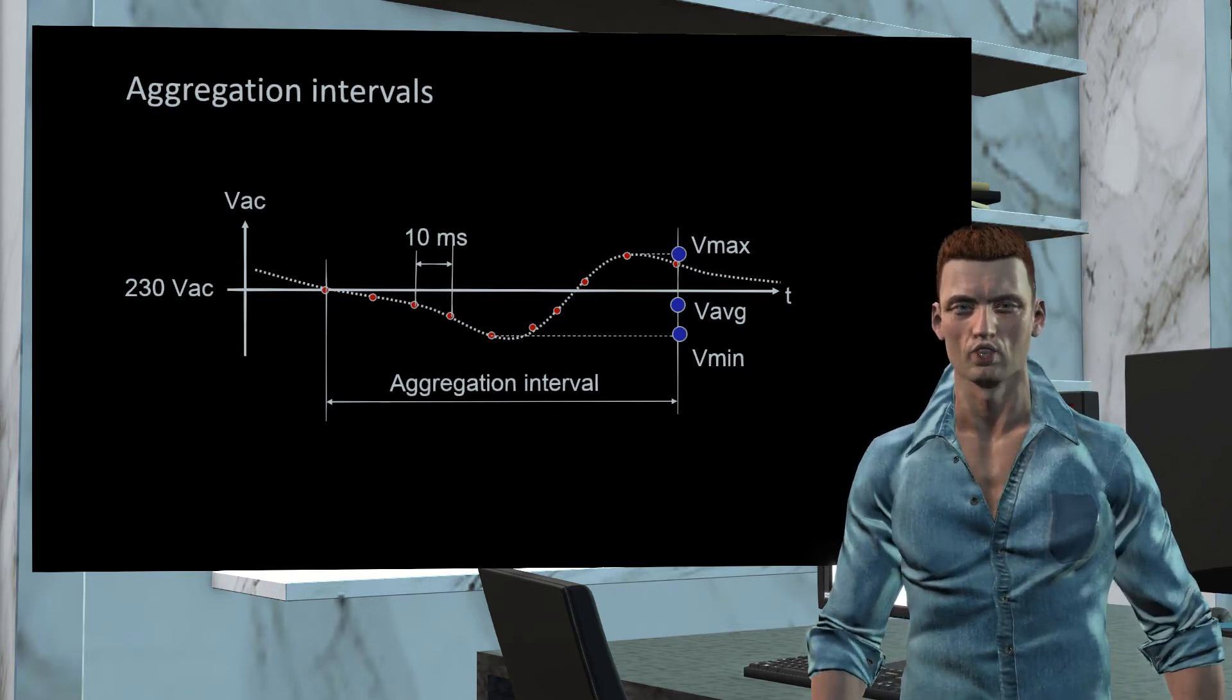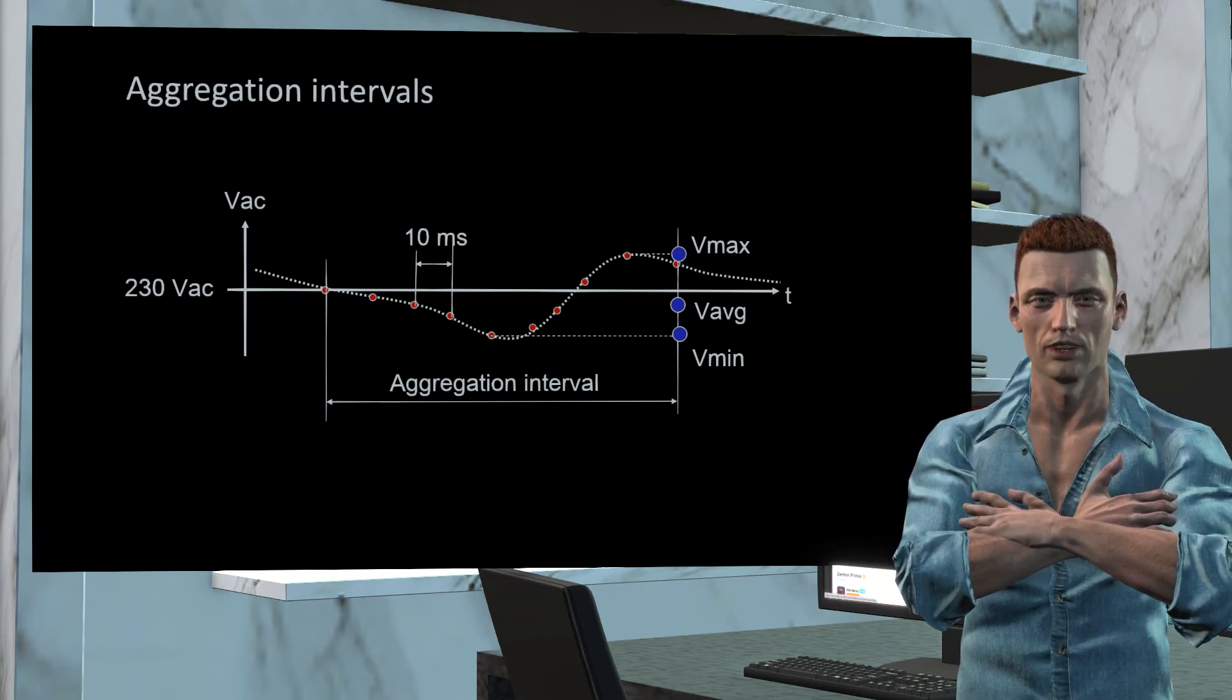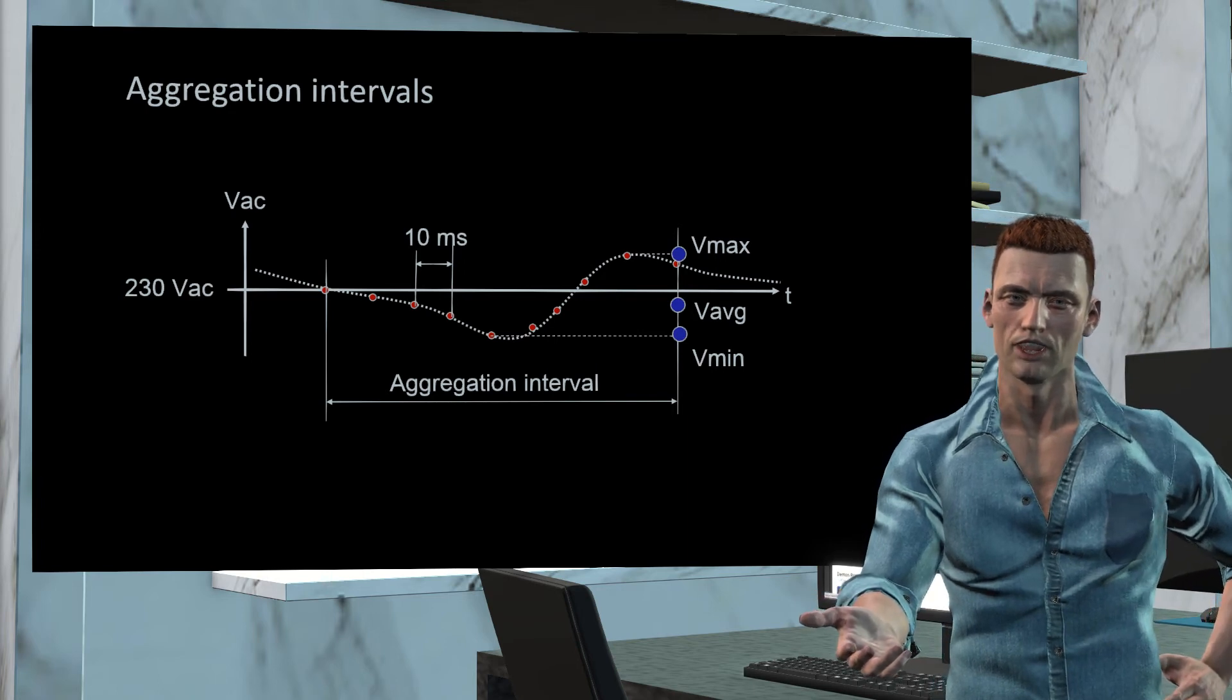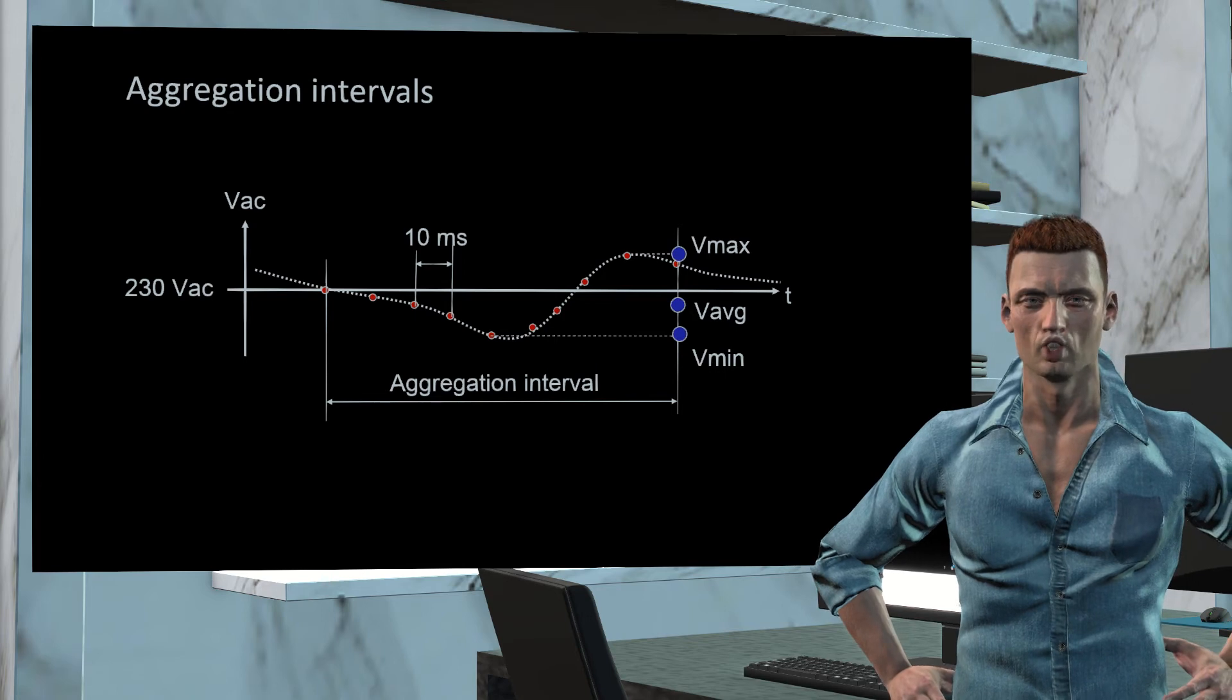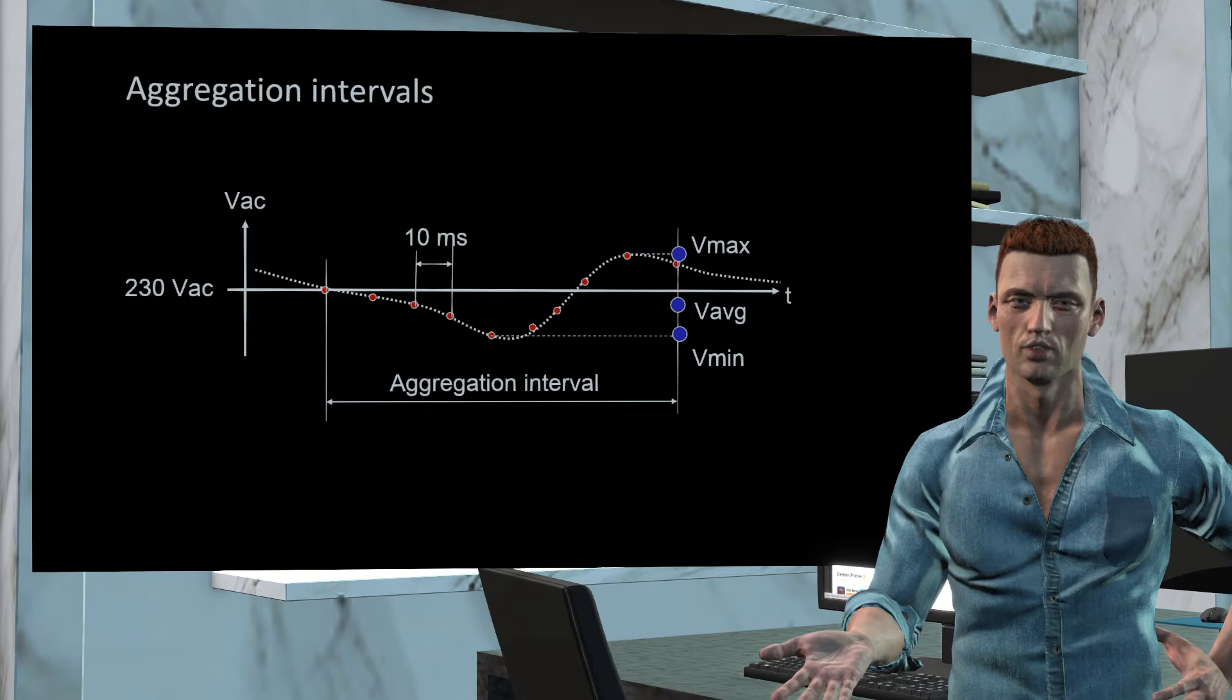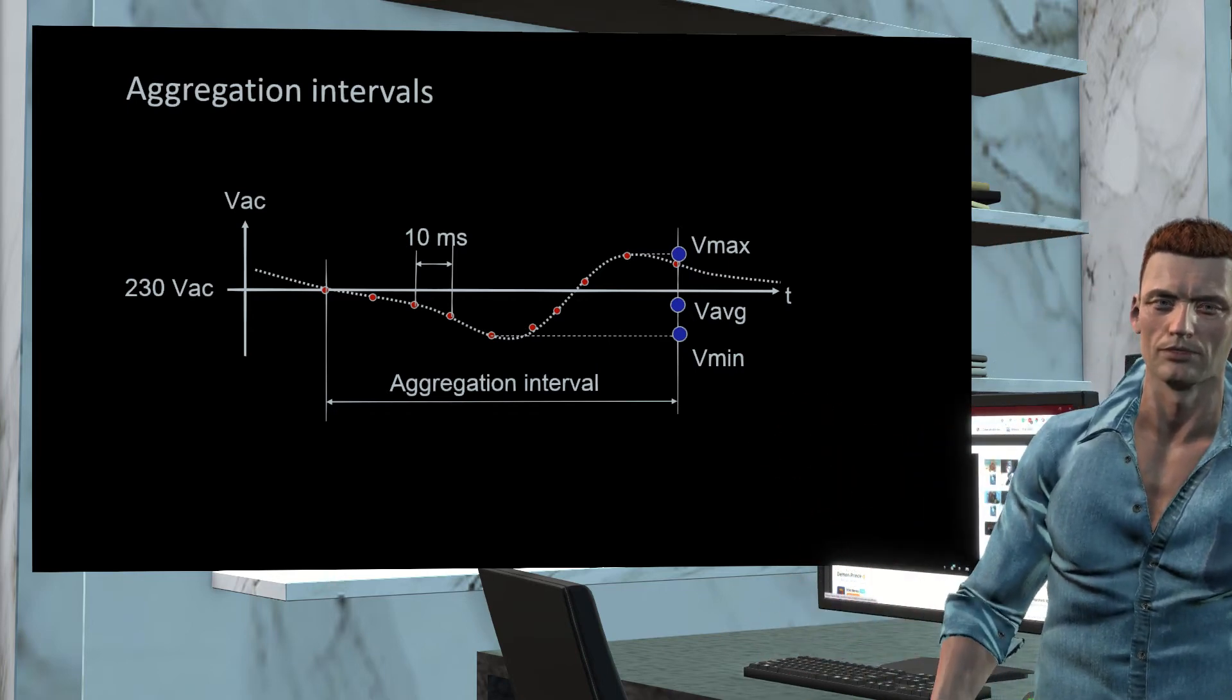These are the aggregation intervals proposed by the IEC 61000-4-30. In addition to these measurement intervals proposed by this standard, Fluke 430 series analyzers allow to define custom aggregation intervals from 250 milliseconds up to 2 hours. In this way we can study records in more detail for special situations, not just power quality.